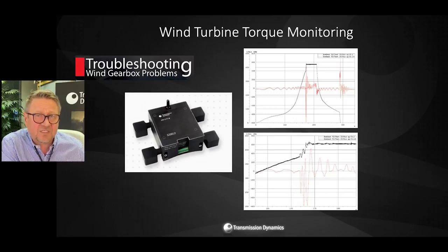So on this inset here we can see the graphs on the top right hand inset. Black curve is showing the speed of the wind turbine during startup. We're starting at 0 speed and gradually climbing up to the speed measured on this intermediate shaft as constant when we effectively assign the wind turbine to the grid, and the red traces are showing the torque. And what we can see, especially at the lower graph here, that we assigned the wind turbine on this occasion just slightly prematurely.